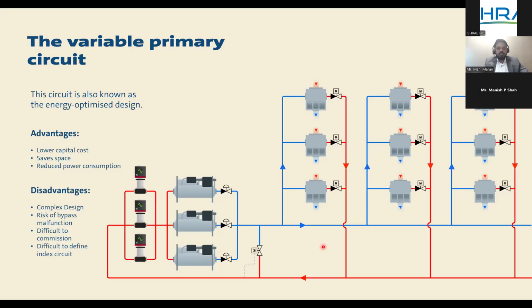So there is a clear advantage on this aspect, but the flip side of the design is that the design is a little complex because we are modulating the flow in an indirect way. It's not the direct way of modulating the flow. That's one challenge. And the commissioning is always a difficult thing because balancing has to be ensured. And then we need to identify the critical load, set point of the differential pressure, and then the pump has to modulate according to all those parameters. It's always the flip side of having variable primary, and it needs a lot of operational tactics to keep the system intact with respect to the efficiency.